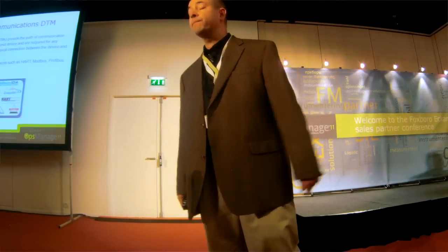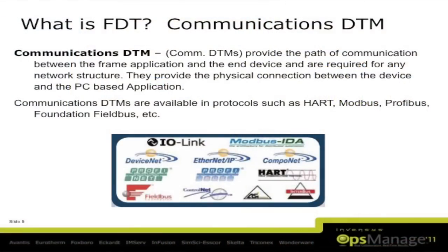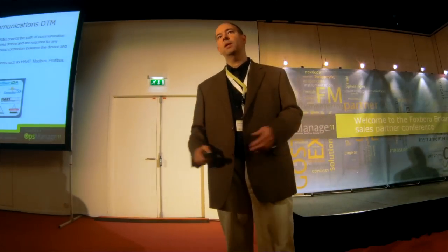To get there, you take the frame and load in the communications DTM. So now that frame can have HART, Fieldbus, Modbus, Profibus, and a host of other protocols. Those particular communications DTMs can be delivered by the vendors. So if you're using something like a multiplexer, they would have a DTM that would handle the communications there. We have historically not developed any of the protocol DTMs except Foxboro, and that's for obvious reasons. We are the only ones that do Foxboro.